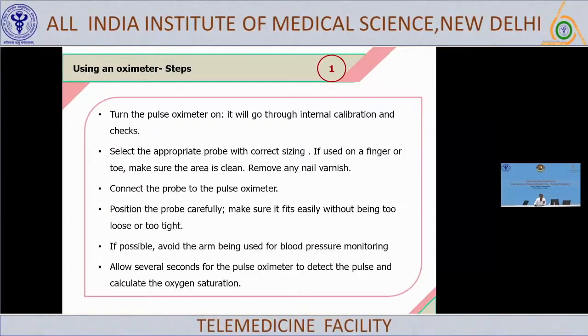Just turn the pulse oximeter on. It will take some time for internal calibration. For that time, whatever readings are coming may not be appropriate. Just wait for a couple of seconds. When the readings stabilize, then you can use them. Select the appropriate size of probe. Connect the probe to the pulse oximeter. Position the probe carefully. It should fit appropriately on the finger on which you are applying it. It is better a bit loose, not too tight.